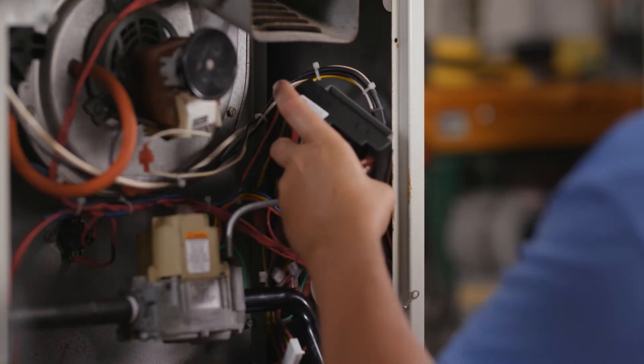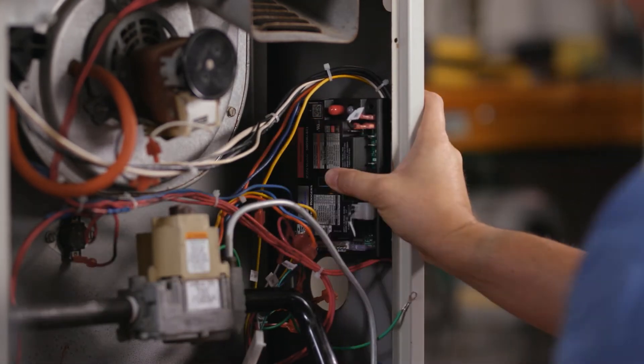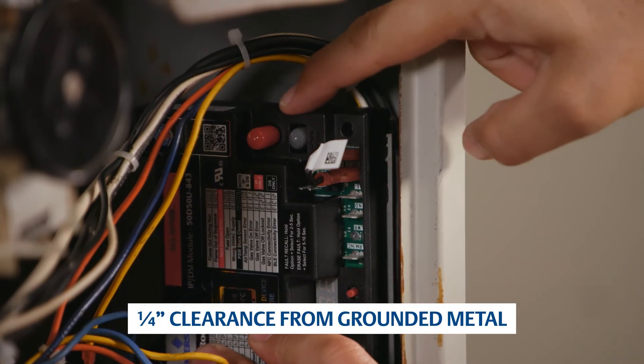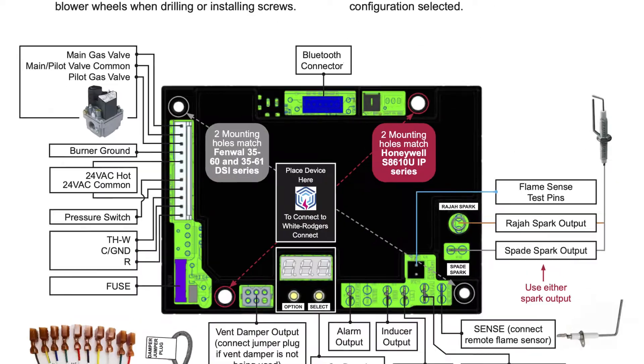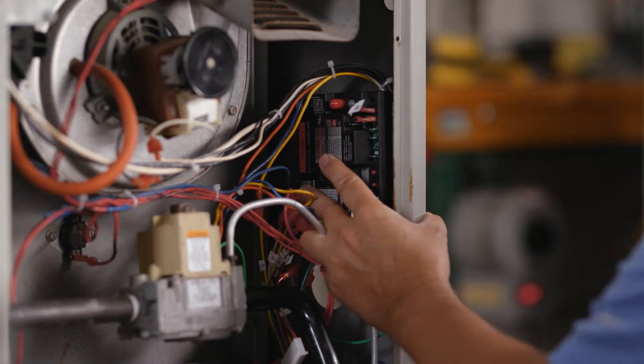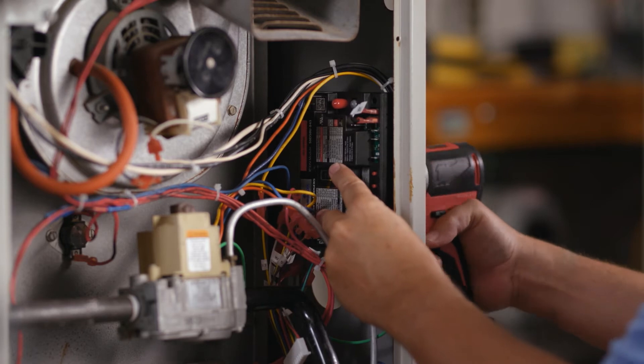The module can be mounted in any orientation. Select a location that will not damage, obstruct, or place stress on the terminations or harness. Ensure there is a clearance of a quarter inch between the sides of the control and the grounded metal. There are four mounting holes located toward the corners of the module. Utilize the two that match the existing module. Mount the 50D50U-843 using the mounting holes and supplied screws.